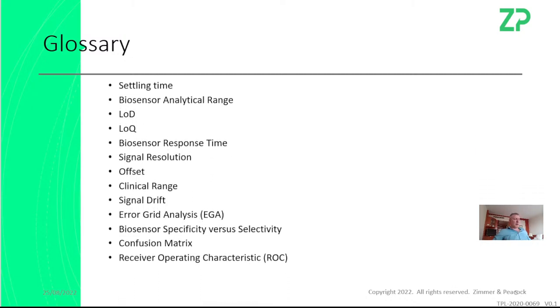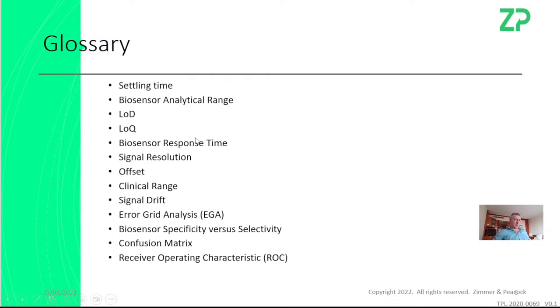For the glossary: when you're talking about biosensors, people often approach us and ask for the characteristics or specification of the sensor. I'll talk about settling time — the time it takes for a sensor to essentially reach its baseline before you can take a measurement. The analytical range is the range over which the sensor will work, which brings us into limit of detection and limit of quantification. And biosensor response time — how quickly will it respond to a change in concentration. Signal resolution.